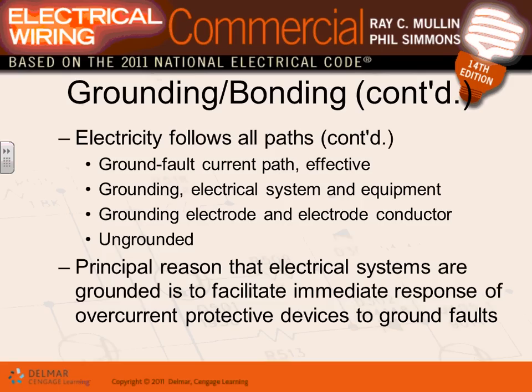So ground fault current. The code requires the ground fault path to be as smooth and as easy and as wide as possible. They allow you to use the EMT conduit, rigid, intermediate, the shell of these conduits as an equivalent ground conductor. Or if it's PVC conduit, you have to pull a conductor inside the conduit to ground all the metallic parts of any electrical equipment. Almost all the electrical equipment made of metallic objects, from your refrigerator to the air handling unit to the chillers and what not, have to be grounded.